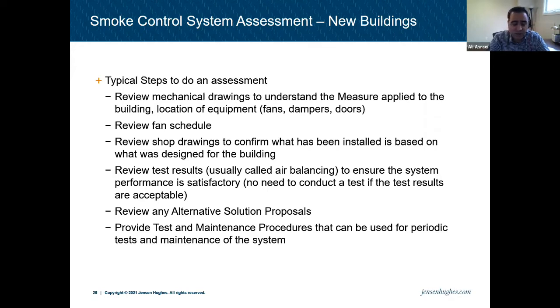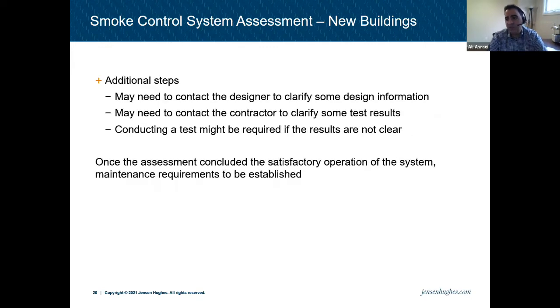And as part of it, we review any alternative solution applications that were provided for the building, just to make sure that we're not missing anything, because sometimes some alternative solutions involve a smoke control system, pressurizing certain areas, venting certain areas. So just to make sure we have everything. And when we have all that, we provide a test and maintenance procedure. Moving forward, they can use that procedure to test the system and maintain it properly. Periodically, it's every month, every 3 months, annually, every 2 years. So it depends on what system you're dealing with. And we give them that procedure and they follow it after that. So that's basically an assessment that we're doing.